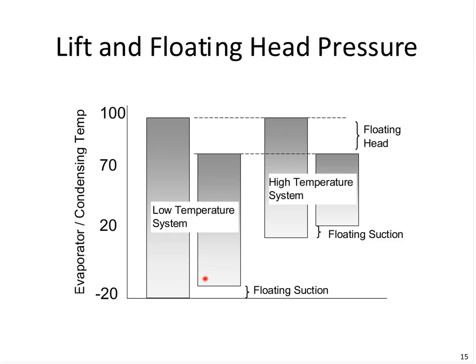And on the higher temperature systems, let's say we're maintaining a 20-degree evaporator, we still can float that where possible, and float the head pressure when Mother Nature allows us to do that. So these are two common things. They do require controls, and in some cases, a commitment to get those to work right.